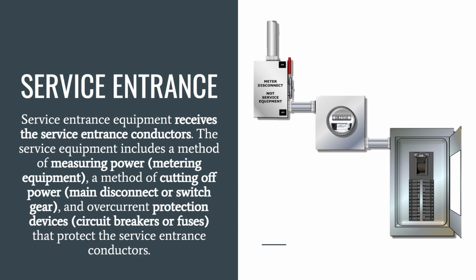The service entrance includes the components that connect the utility-supplied wiring, the service lateral or service drop, to the service disconnect, excluding the utility's metering equipment. Service entrance equipment receives the service entrance conductors. The service equipment includes a method of measuring power, the metering equipment, a method of cutting off power, the main disconnect or switchgear, and overcurrent protection devices, the circuit breakers or fuses, that protect the service entrance conductors.